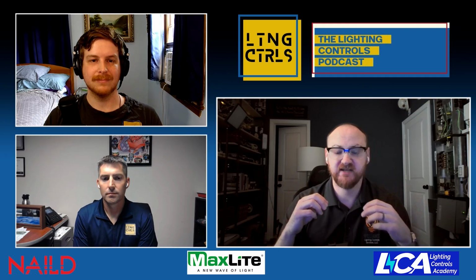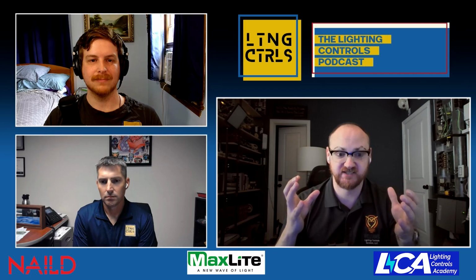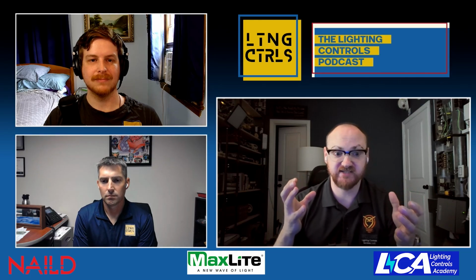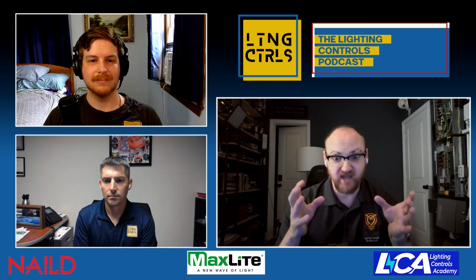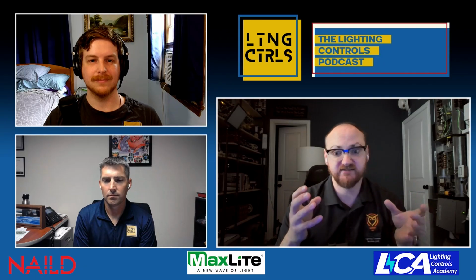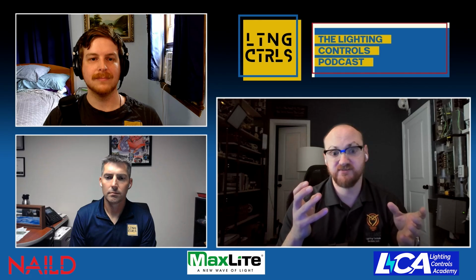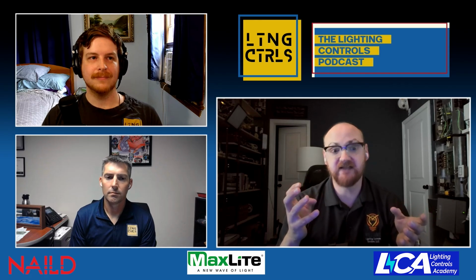Then I'm not necessarily looking to get the lights to completely turn off. I'm looking to see if the room is coming to a status quo as far as airflow, the ceiling grid not shaking, things like that. Everything else about that sensor should be good to where it can remain stagnant and still for 20 minutes or whatever the time delay is, as long as the contractor says they haven't touched those, they're at their defaults, then that sensor should work. I'll rely, to some degree, on the punch list process later on, in case there's a bad sensor out there somewhere that never turns off.